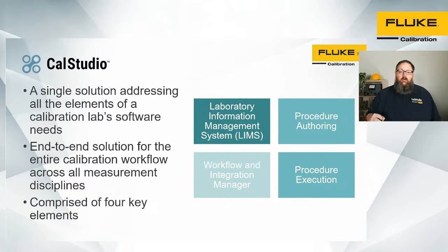The third element is the calibration execution environment, where we run those procedures that we've authored, built on our universal measurement model that allows us to consider all the measurement parameters and all of the attributes and pieces of the measurement uncertainty and the measurement equation, the measurement formula that are at play, so that we can address all of those disciplines consistently in the same way.